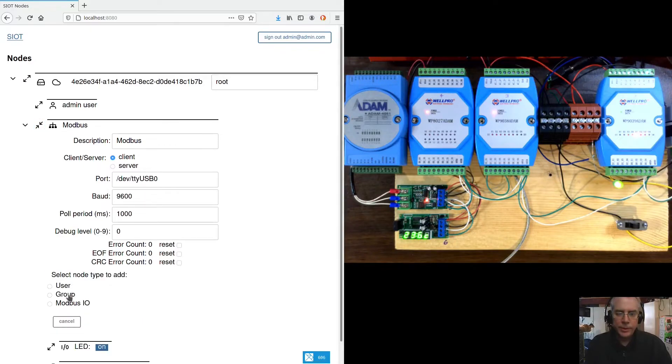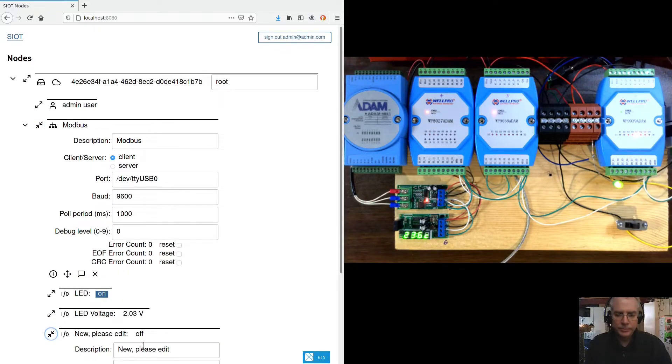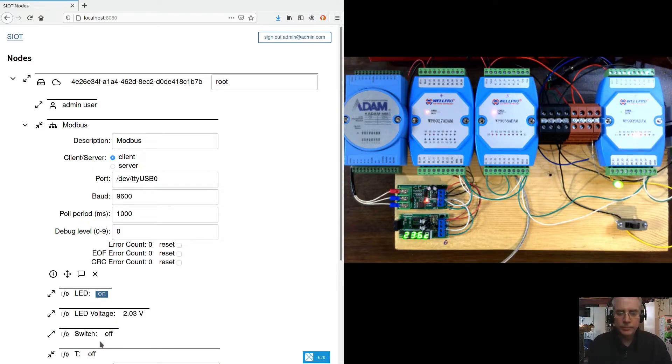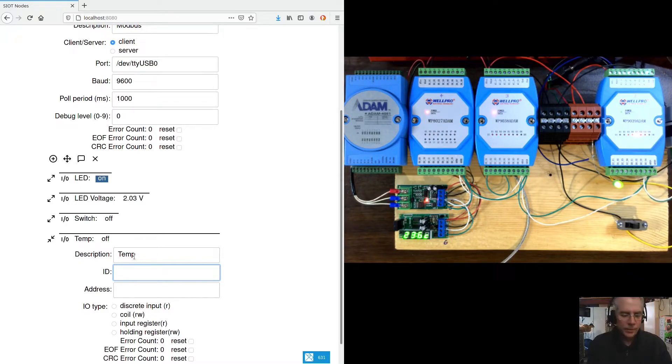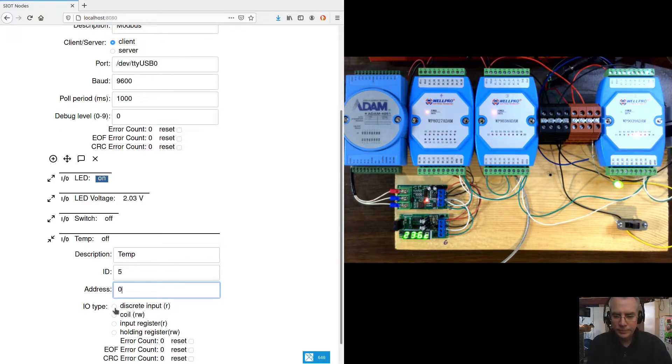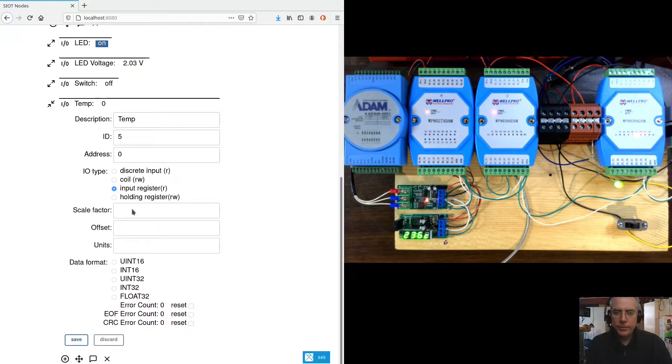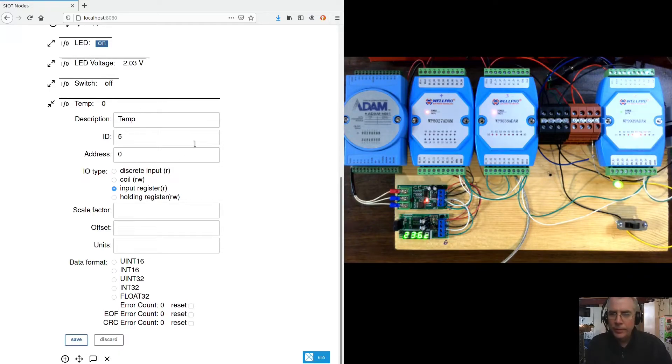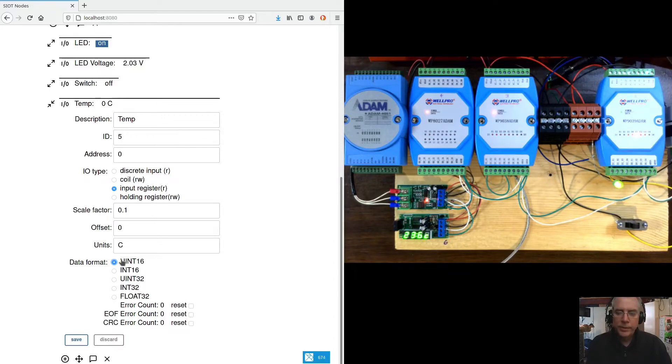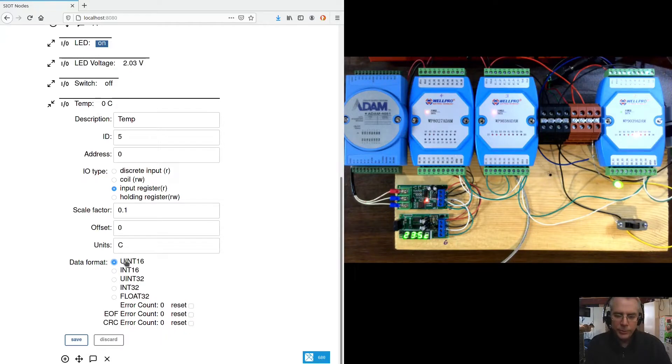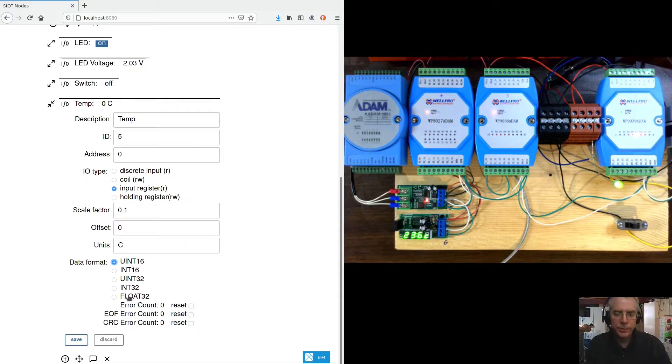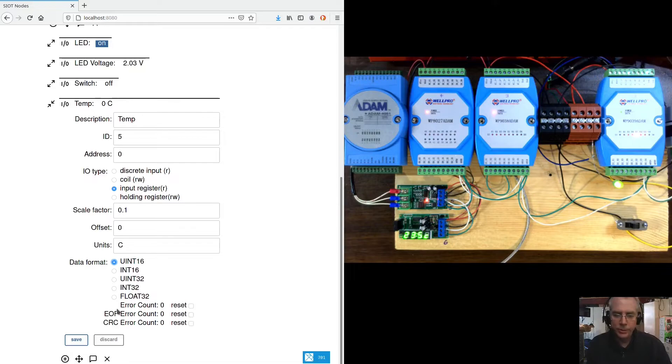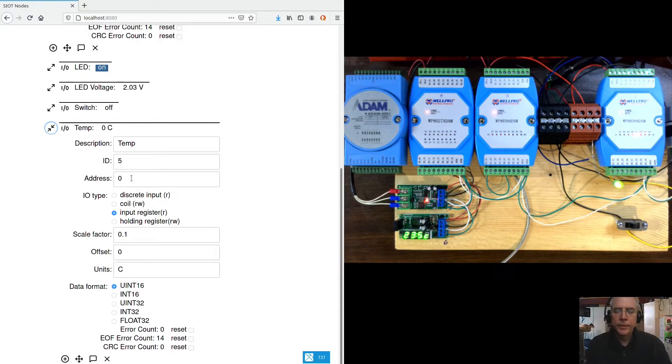We can also add a temperature sensor. And we'll read the device 5, 0. And the scale factor for these temperature sensors. I think it's just divide by 10, so we'll do 0.1. And C for degrees C. So Modbus devices present data in a number of different ways. The most common is a 16-bit integer. Sometimes they'll pack data into 32-bits and even 32-bit floats. So we can decode any of these data types. We just have to tell it which one. So we'll save that.